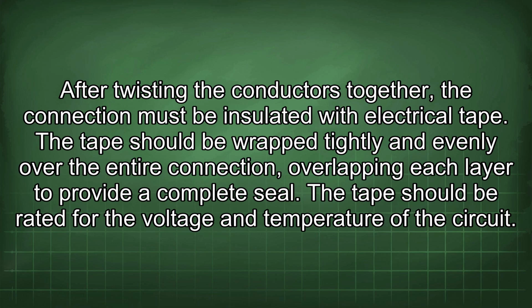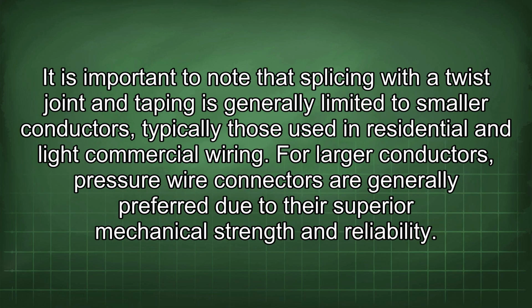After twisting the conductors together, the connection must be insulated with electrical tape. The tape should be wrapped tightly and evenly over the entire connection, overlapping each layer to provide a complete seal. The tape should be rated for the voltage and temperature of the circuit. It is important to note that splicing with a twist joint and taping is generally limited to smaller conductors, typically those used in residential and light commercial wiring. For larger conductors, pressure wire connectors are generally preferred due to their superior mechanical strength and reliability.